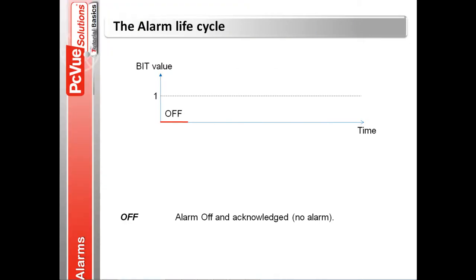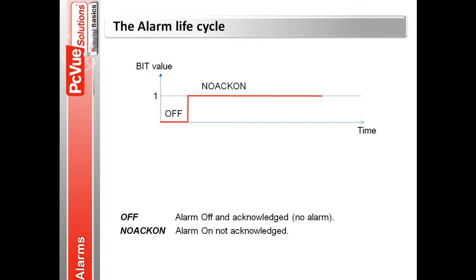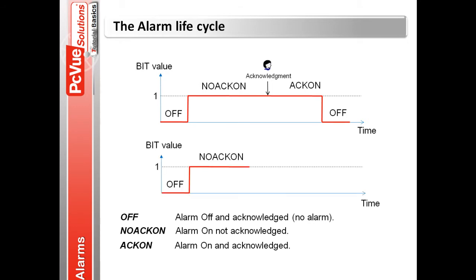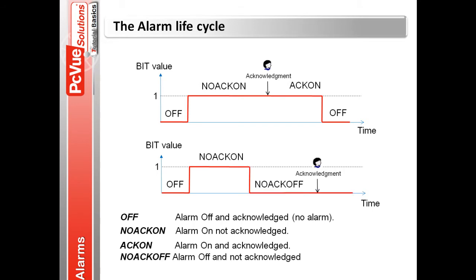First, the bit value is equal to zero — the alarm is off and acknowledged; there's no alarm. The alarm is on and has not been acknowledged by a user. A user acknowledges the alarm, which becomes on-acknowledged. The alarm becomes off when the bit value goes to zero. If the alarm is on and not acknowledged, and the bit value goes to zero, the alarm becomes off-not-acknowledged, and then off whenever the user acknowledges it.